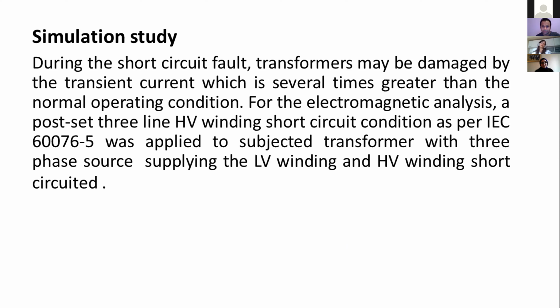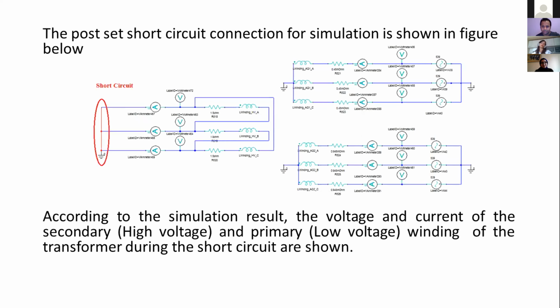In the simulation study, during a short circuit fault, transformers may be damaged by the transient current, which is several times greater than the normal operation condition. For the electromagnetic analysis, a post-set three-line HV winding short circuit condition as per IEC 60076-5 was applied to the subject transformer, with a three-phase source applied to the LV winding, low voltage winding, and the high voltage winding short circuited. The post-set short circuit condition of the simulation is shown in the figure.